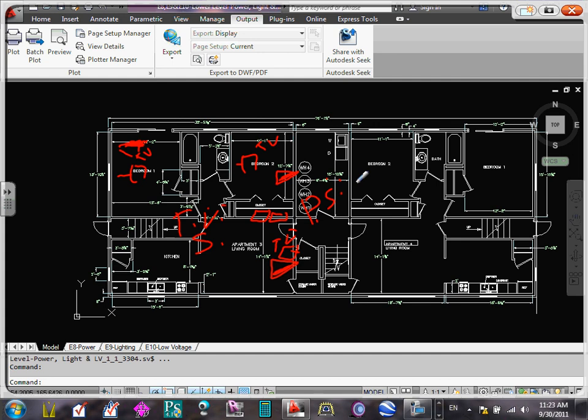The only thing I want you to show right at the bottom here, somewhere in this area, is the same thing. This will be main phone splitter, and the one next to it will be main TV splitter, which is basically for the coaxial. What I'm trying to indicate, and you'll see this when we do the risers, is a coaxial coming to the building, 1 in, 4 out, each one going to every apartment. Inside the apartment, every out becomes an in and goes out again for another 4.